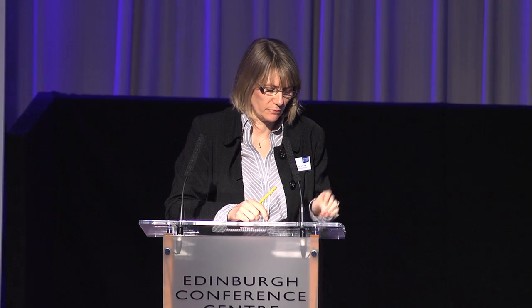to be able to benchmark against. That means that once you have a defect-free trace, you would then run, for example, a trace every 24 hours, sometime during the night when nobody's using the system. Compare with the original design, you see the defective point, the time scale of the wave travel will tell you where the defect is, and then you can go and remedy that.